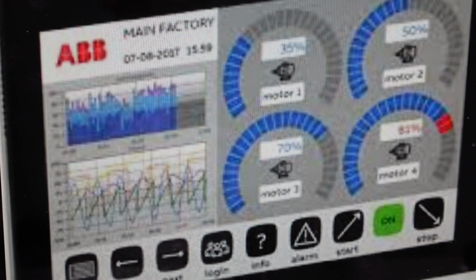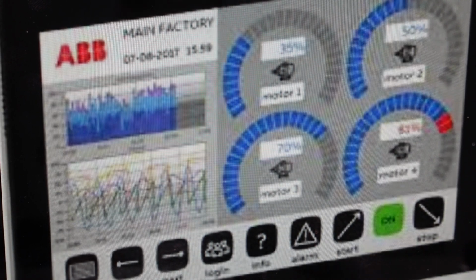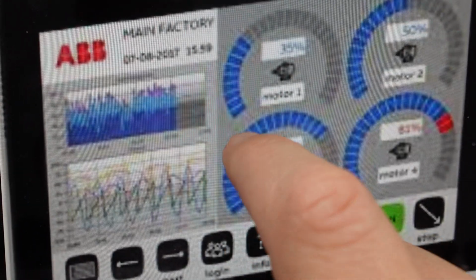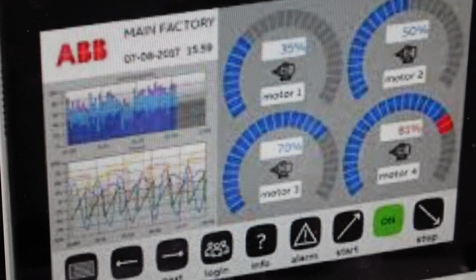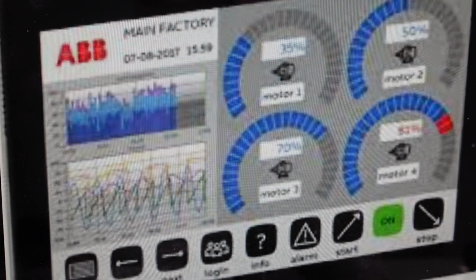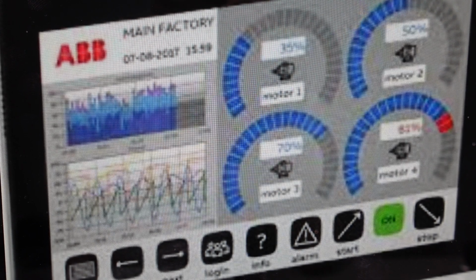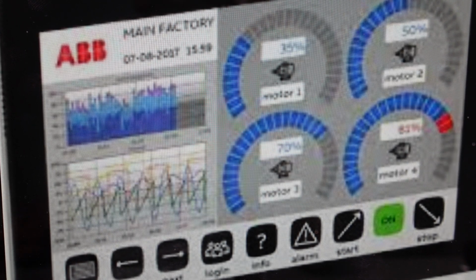We're just going to start by turning off the panel. And then what we're going to do is we're going to turn the panel on and we're going to immediately start tapping on the screen, in the middle of the screen as we're turning it on, and you'll see it'll eventually show up on the screen, "Tap is detected, going to the config mode." Once that happens, you can stop tapping on the panel and just wait until the rotating menu is loaded.